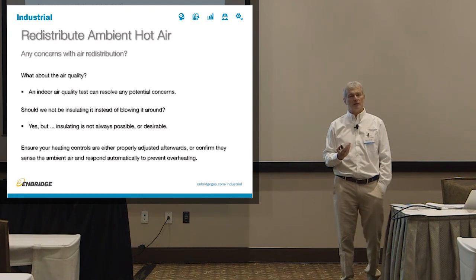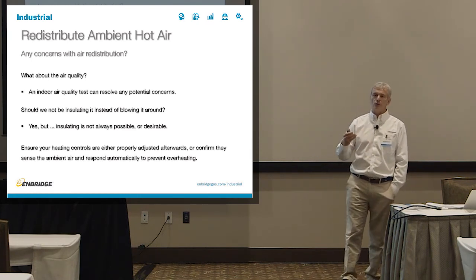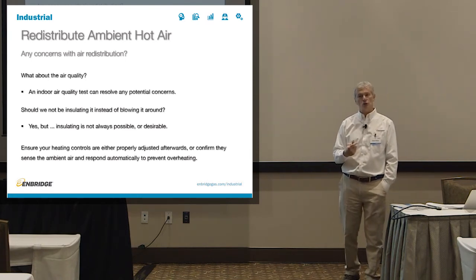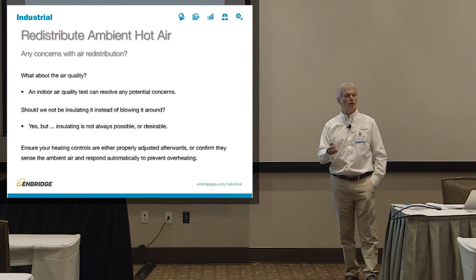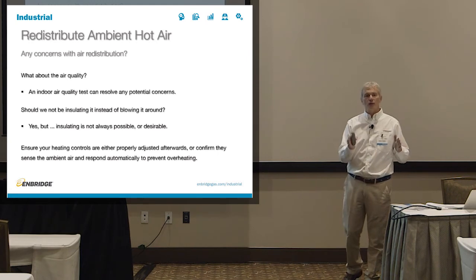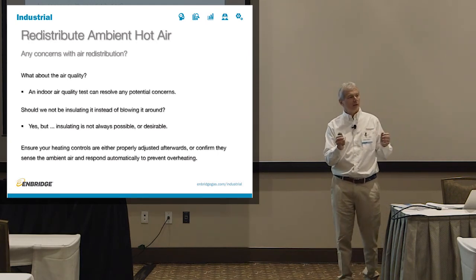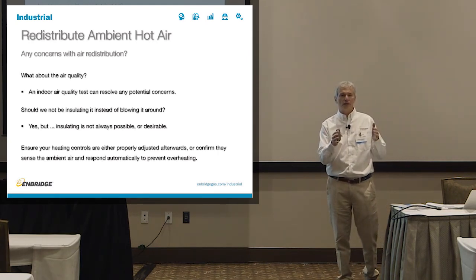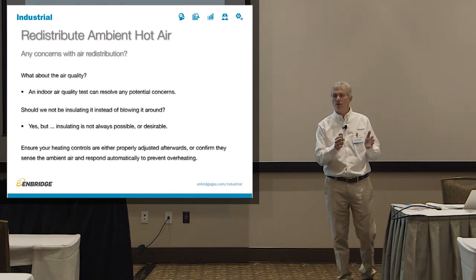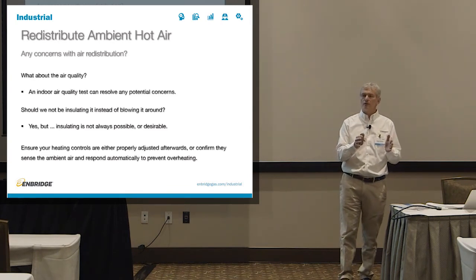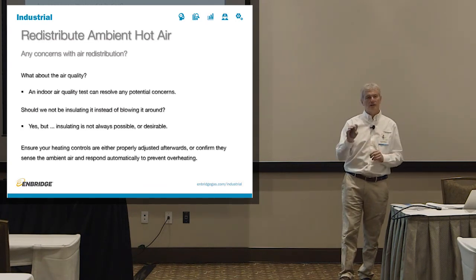That makes sense. But usually it's really hard to add insulation to a convection oven, for example. It's not really a good thing to add insulation on top of your regular oven shell, because you will get condensation, and if the oven was not designed for that, you will actually ruin the oven much faster than you would otherwise. So you don't want to necessarily insulate everything. There's times when you can, and there's times when you cannot.